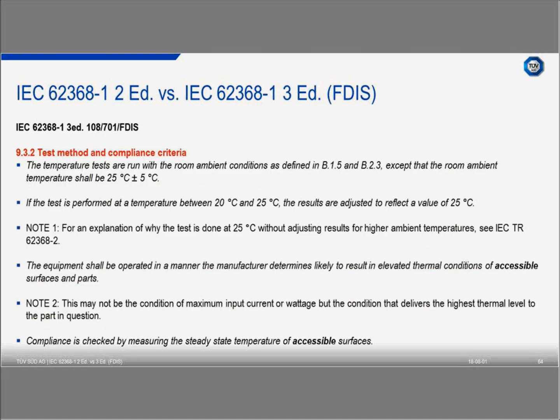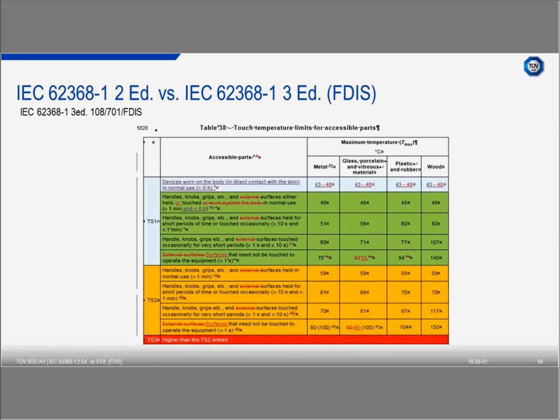This is the topic about measurement of touch temperature. There is a change here: we can measure that at a temperature of 25 degrees plus or minus 5 degrees, but we have to come back to the result adjusted for 25 degrees. And if we go to the table, we have a new accessible part here.